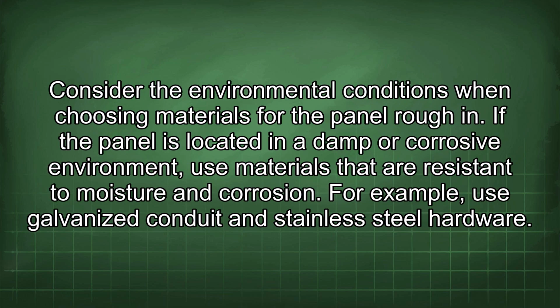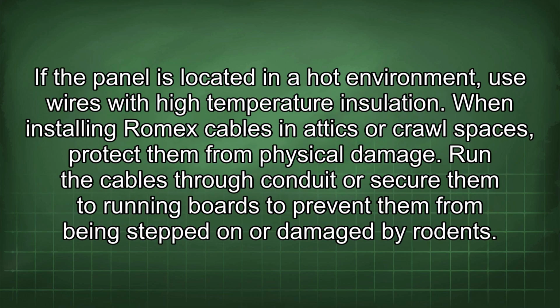Consider the environmental conditions when choosing materials for the panel rough-in. If the panel is located in a damp or corrosive environment, use materials that are resistant to moisture and corrosion. For example, use galvanized conduit and stainless steel hardware. If the panel is located in a hot environment, use wires with high temperature insulation.